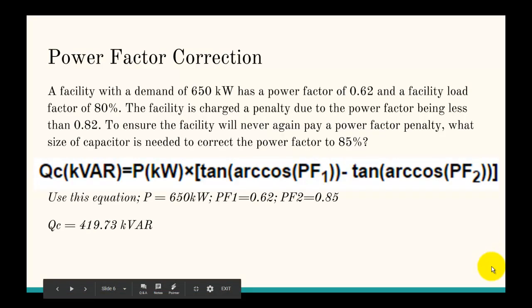So next, let's do a power factor correction problem. So, this is a facility with a demand of 650 kW has a power factor of 0.62 and a facility load factor of 80%. The facility is charged a penalty due to the power factor being less than 0.82. To ensure the facility will never again pay a power factor penalty, what size of a capacitor is needed to correct the power factor to 85%?